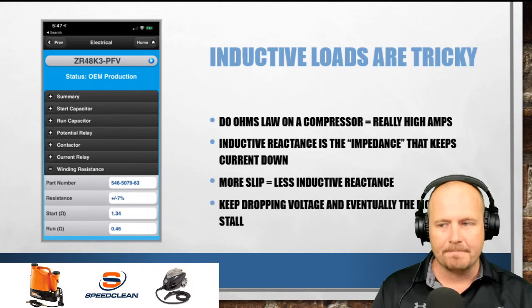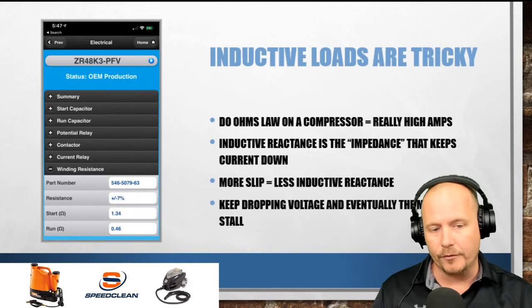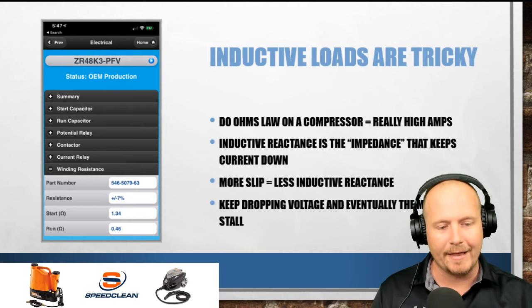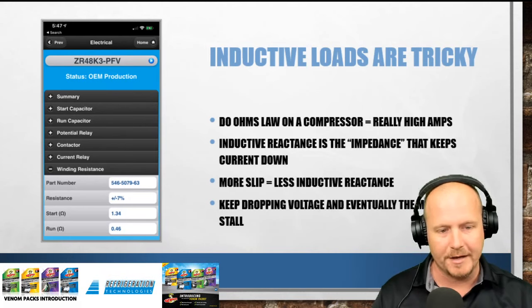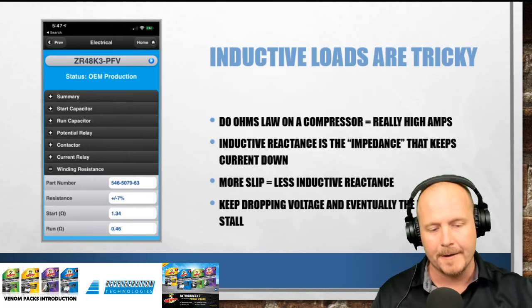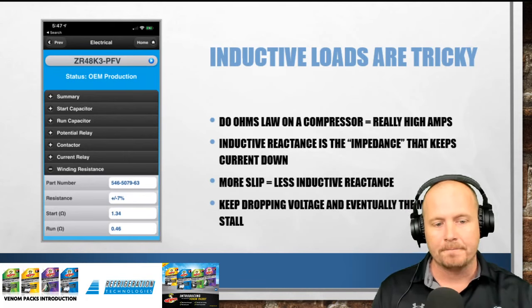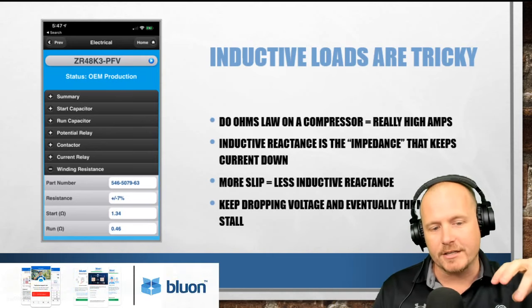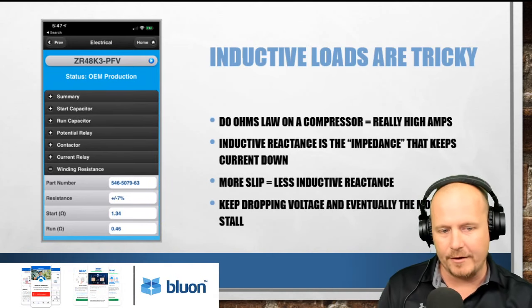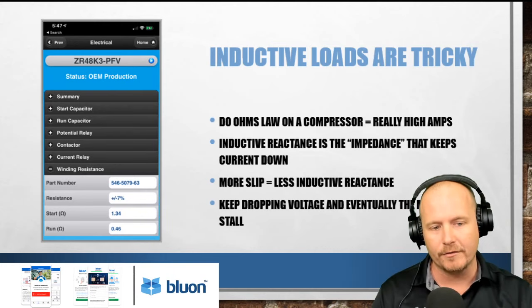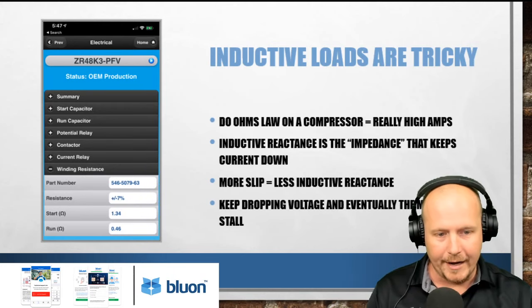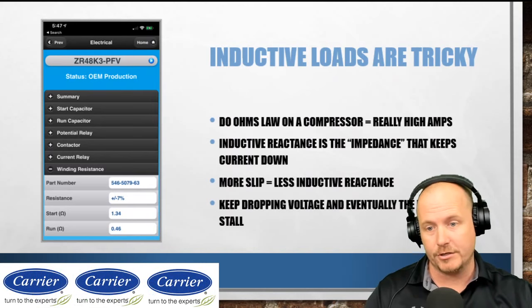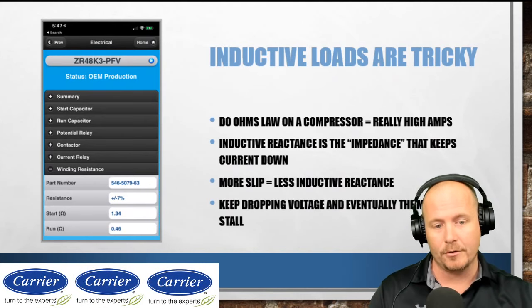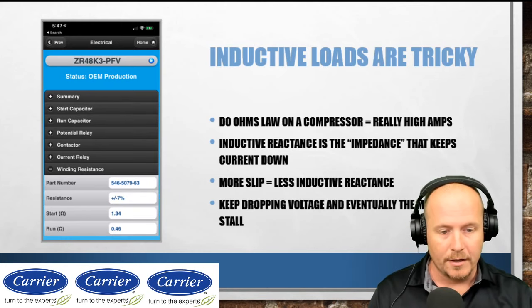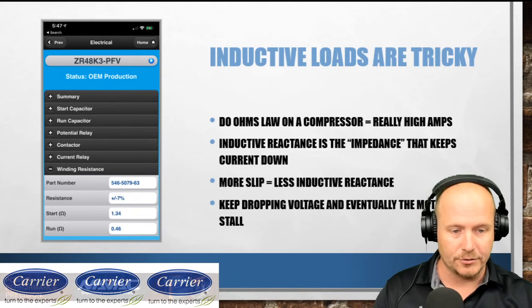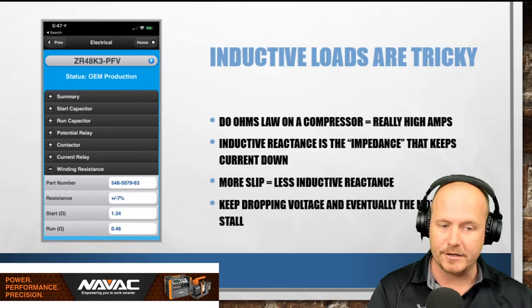The answer is it varies by the motor and the load that the motor's under. But at least in my lab and with the motor that I've got, and it's a regular PSC blower motor, it's got a capacitor on it, all that. When you drive the voltage down, the current also goes down. It just doesn't go down as fast as the voltage, meaning that you have two things going on at once when you drive the voltage down on a motor. On one hand, you're decreasing the applied voltage so that motor starts to slip. As that motor starts to slip, it starts to use the voltage applied to it, the potential applied to it, less efficiently. More of it is going to heat.